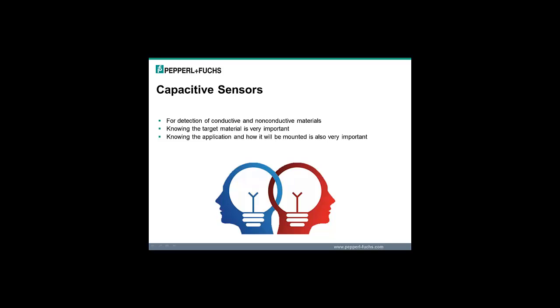Capacitive sensors can detect both conductive and non-conductive materials. An inductive sensor can detect only metal, but a capacitive sensor can detect a variety of materials. Knowing the target material and how the capacitive sensor will be mounted are very important in determining whether a capacitive sensor will work in your application.